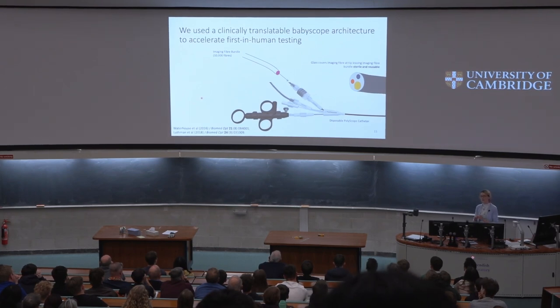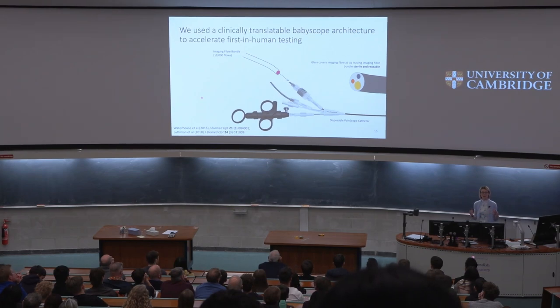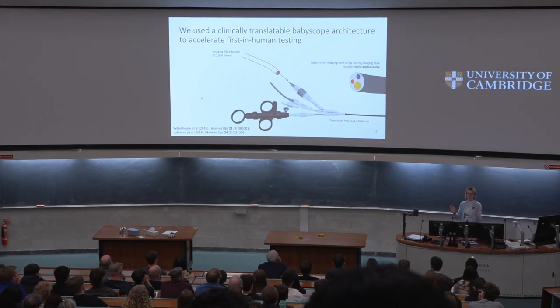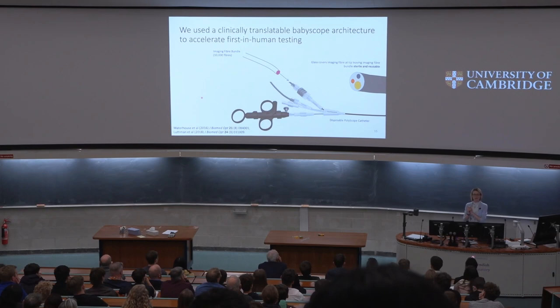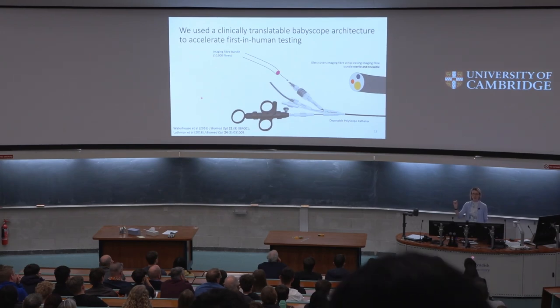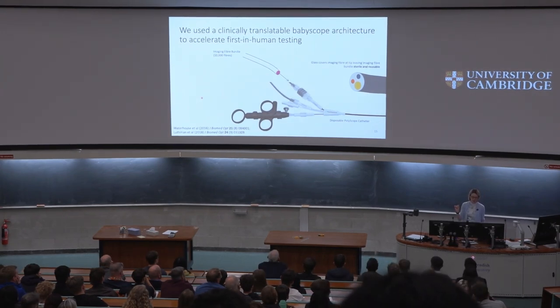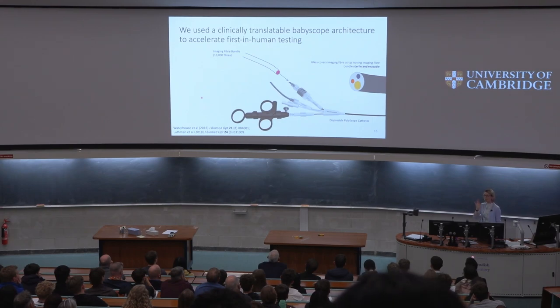This is a very low-resolution imaging device. If you think about fiber optics used for telecommunications, they transfer light very effectively, but to build up spatial information, we bunch a load of them together. Typically we bunch around 10,000 fibers into one bundle, and each individual fiberlet is a single pixel. So instead of megapixel quality imaging, we have kilopixel quality imaging, which doesn't sound so impressive, but it does at least give us a picture from which our endoscopist can visualize.